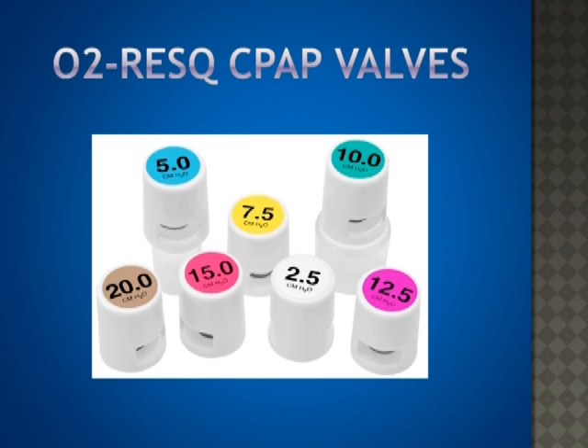O2 CPAP valves provide fixed pressure at any flow rate. The O2 CPAP valves are attached directly to the elbow of the circuit. The most commonly used pressures are 5.0, 7.5, and 10 centimeter CPAP valves. Our protocol will utilize the 7.5 and 10 centimeter CPAP valves. They can be easily changed to any pressure. The circuit also has an anti-asphyxiant valve which allows fresh air intake and prevents exhalation into the tubing in the event of no fresh gas flow.